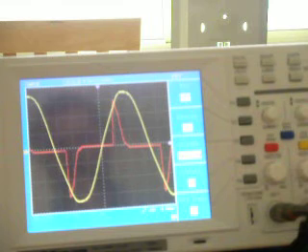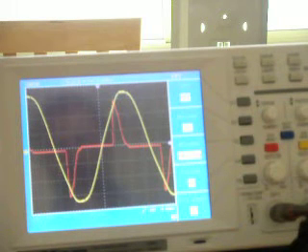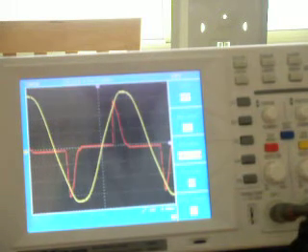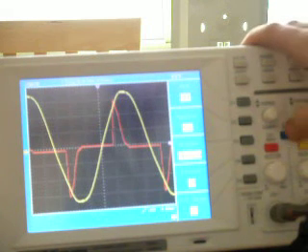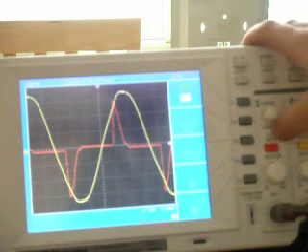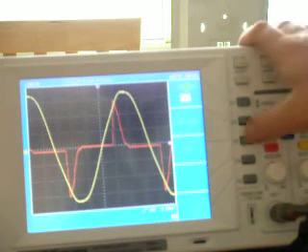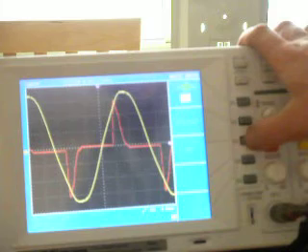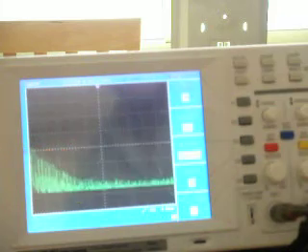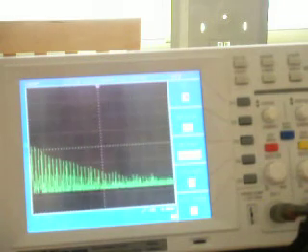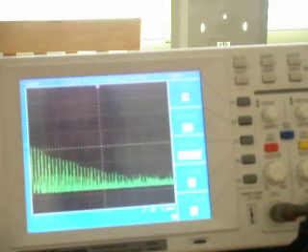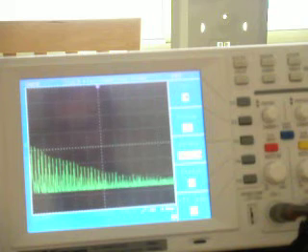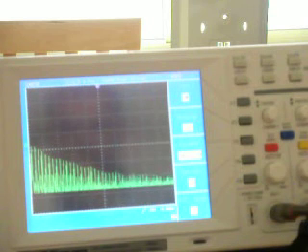We're going to look at this in the frequency domain and you will see that there's a lot of really weird frequencies on the main system when this fluorescent light is in service. As we can see, we've got a lot of spiked frequencies.